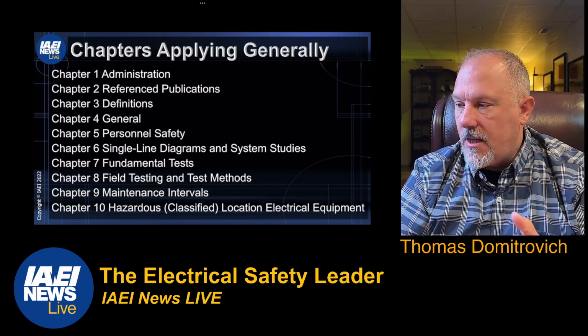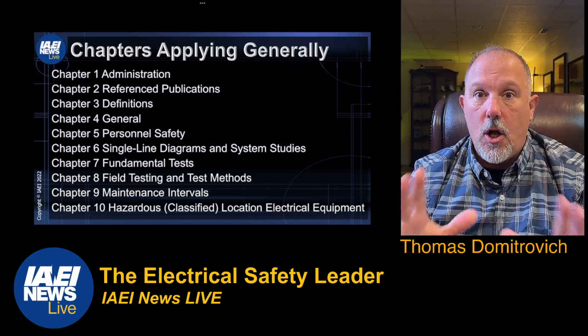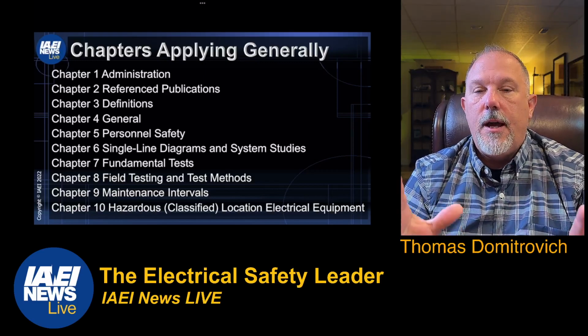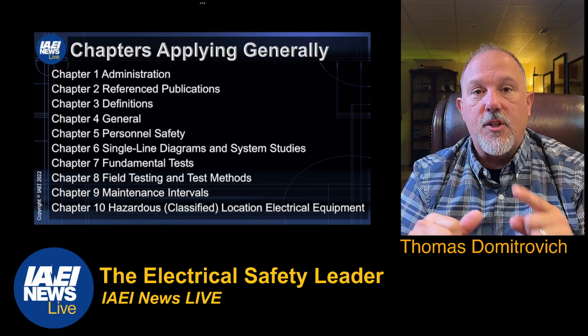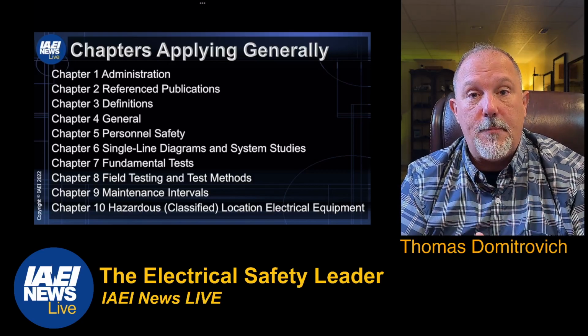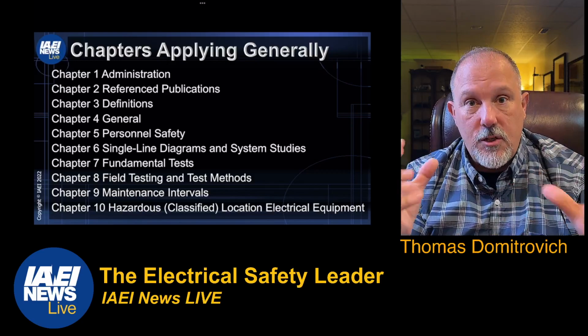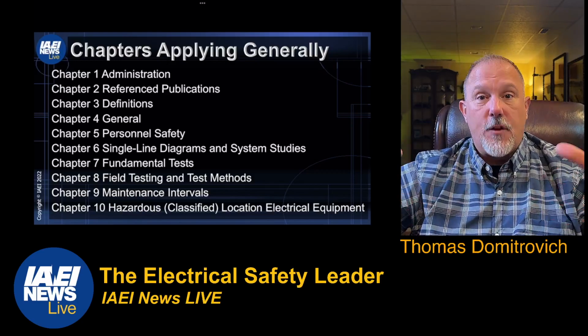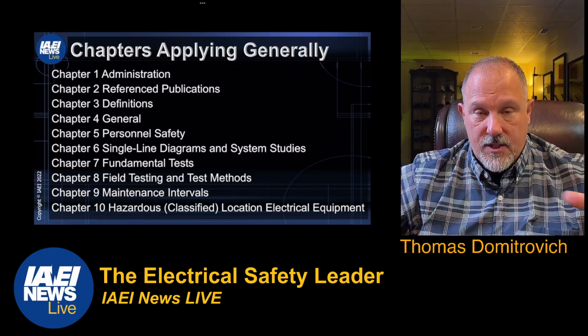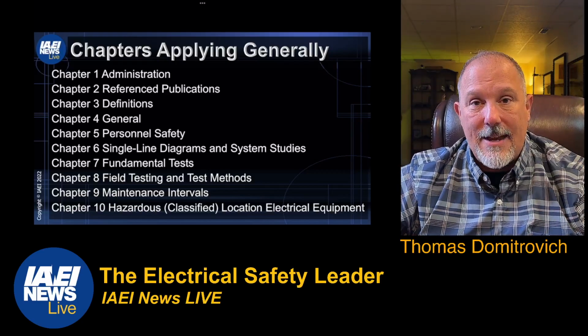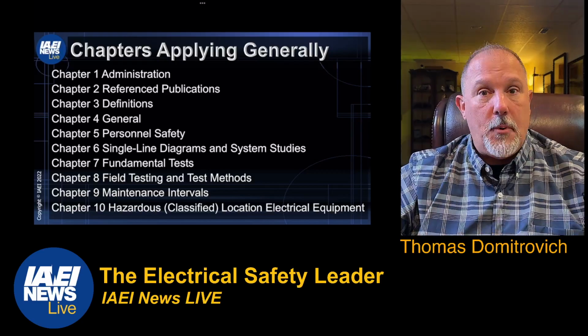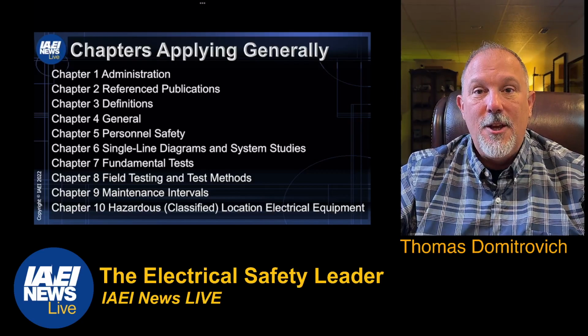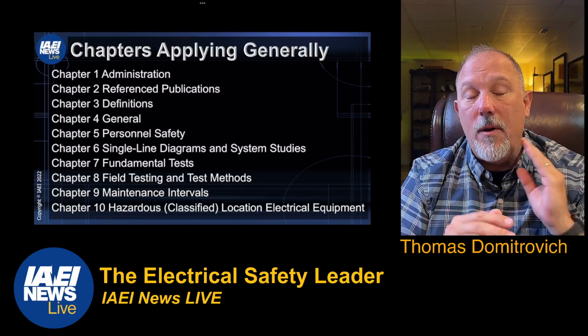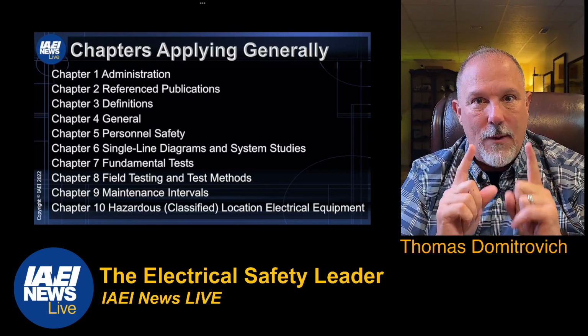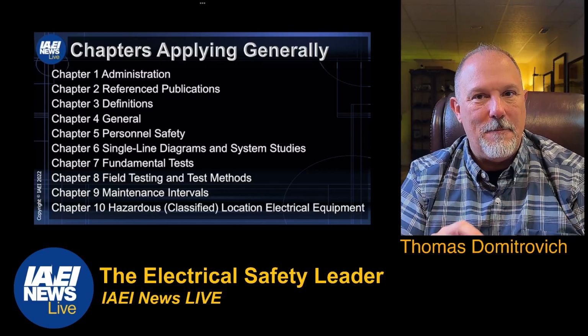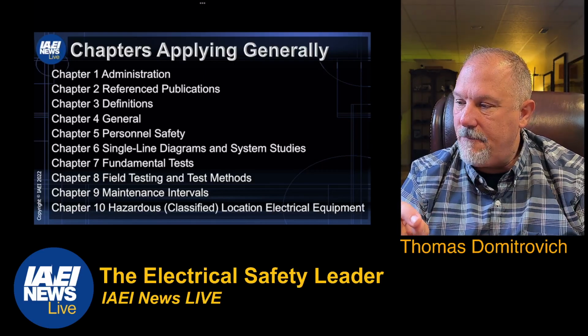And then you have your single line diagrams—very important—and all of your studies, very important. Your single line diagram helps you do what? From a grounding and bonding perspective, if you have a fault in your system and want to make sure the integrity of the grounding and bonding is still intact, you don't have to test every point in your power distribution system. You can isolate just the equipment you want to focus on if you have a good one-line diagram. I can't stress that enough.